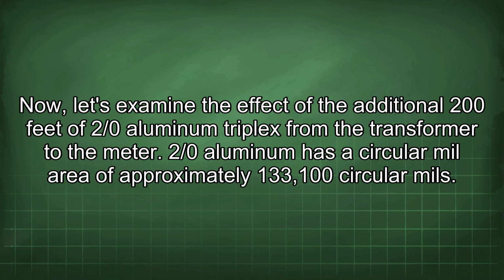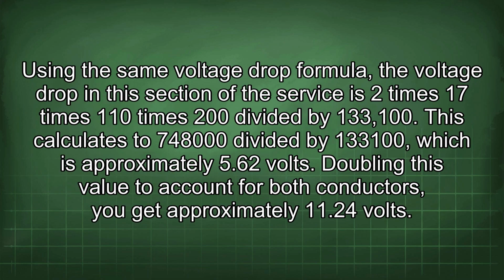Now, let's examine the effect of the additional 200 feet of 2/0 aluminum triplex from the transformer to the meter. 2/0 aluminum has a circular mil area of approximately 133,100 circular mils. Using the same voltage drop formula, the voltage drop in this section of the service is 2 times 17 times 110 times 200 divided by 133,100. This calculates to 748,000 divided by 133,100, which is approximately 5.62 volts.